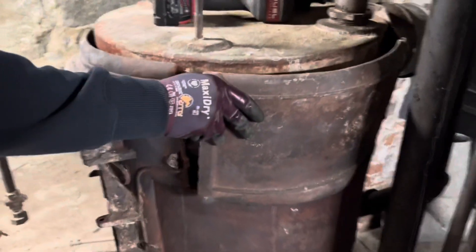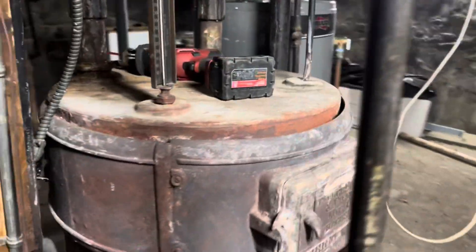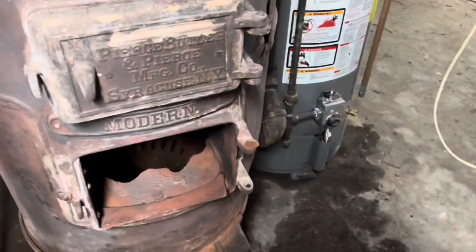Gravity hot water — straight street pressure in, no backflow valve, no pressure relief valve on this boiler. And this boiler failed. It had been working since 1905, and it blew apart. Cracked out the back and knocked all the asbestos off. This was a catastrophic situation — I'm shocked that the house didn't burn to the ground.